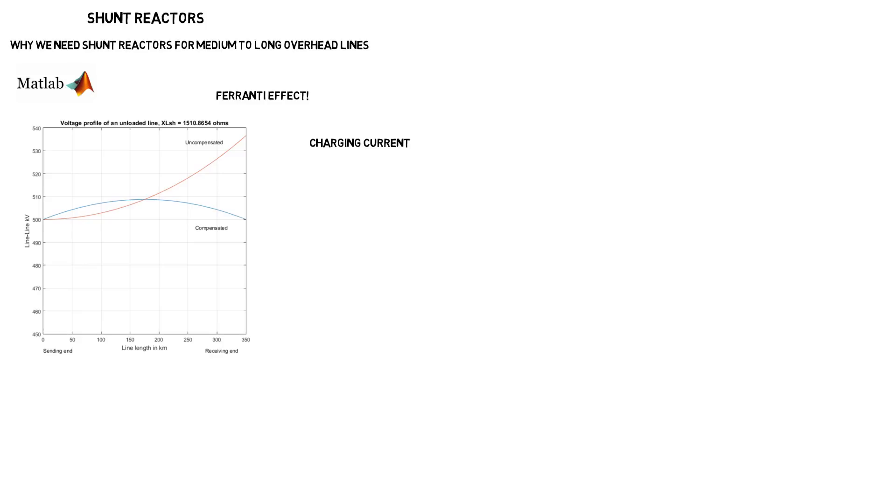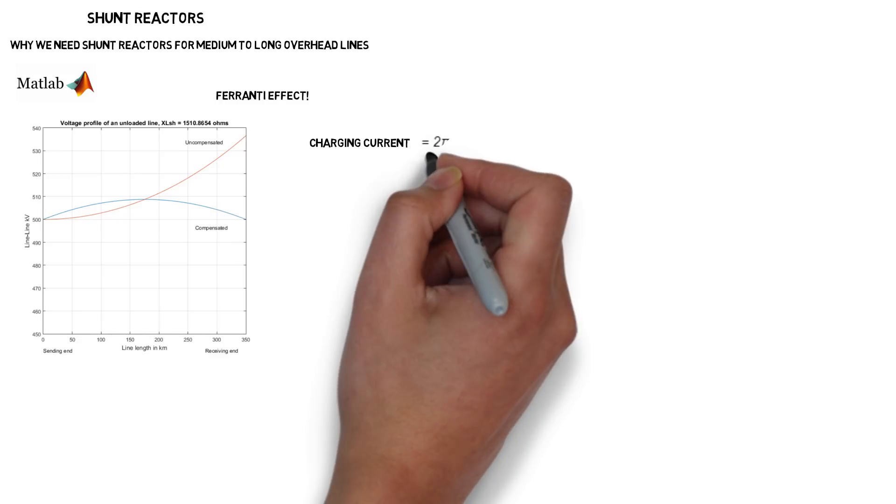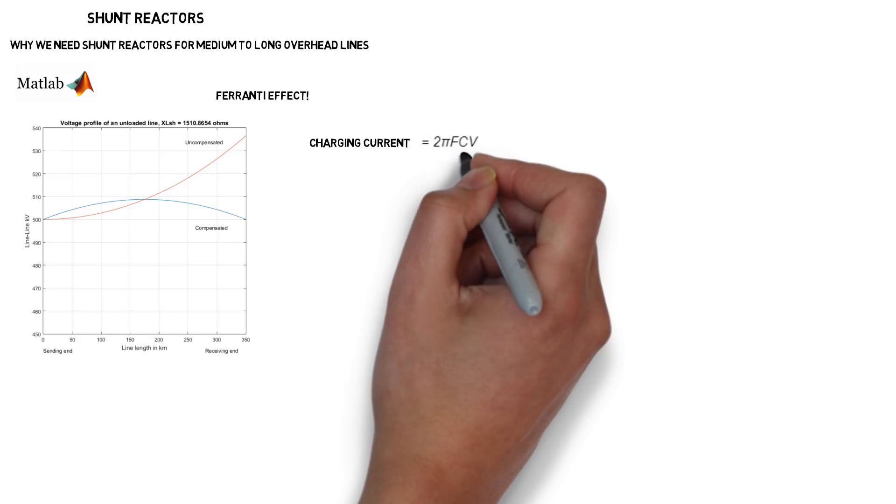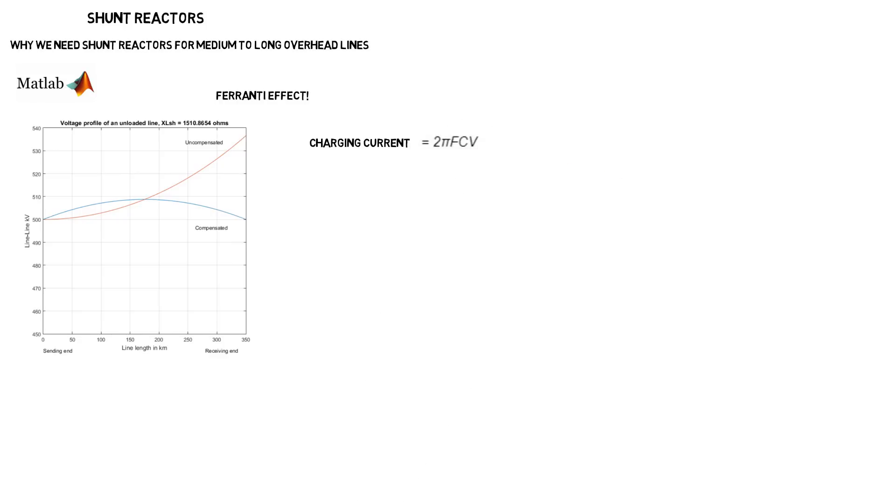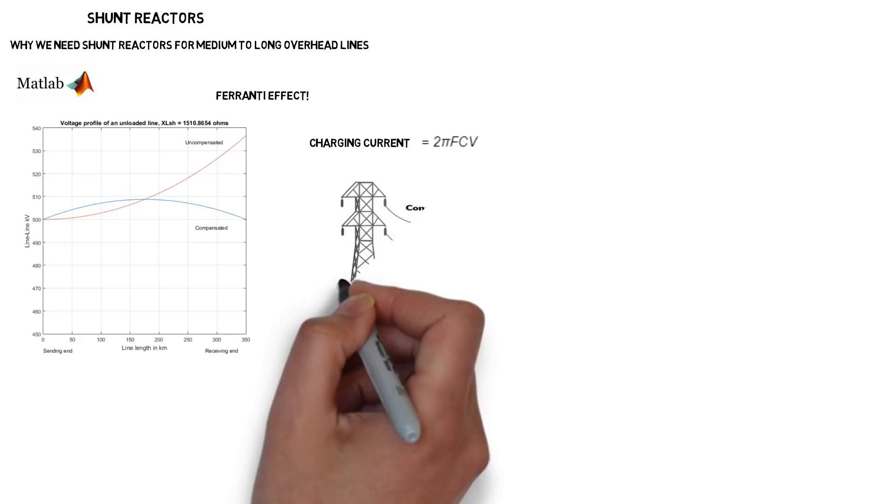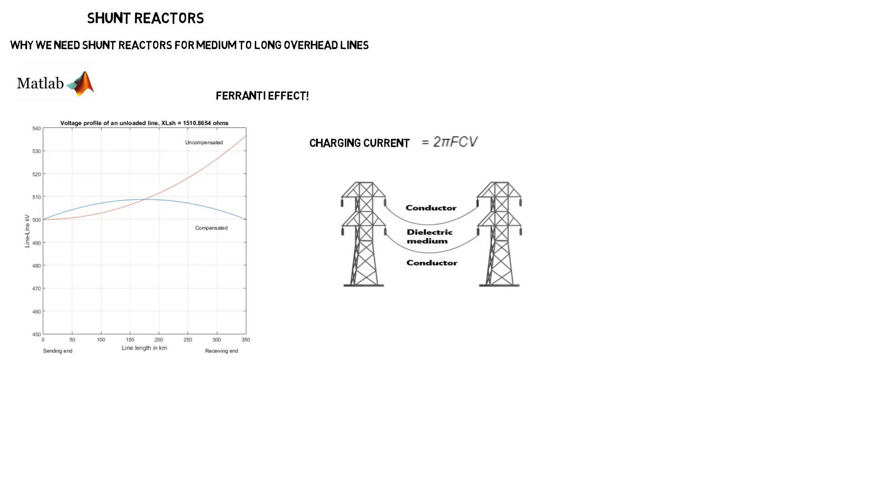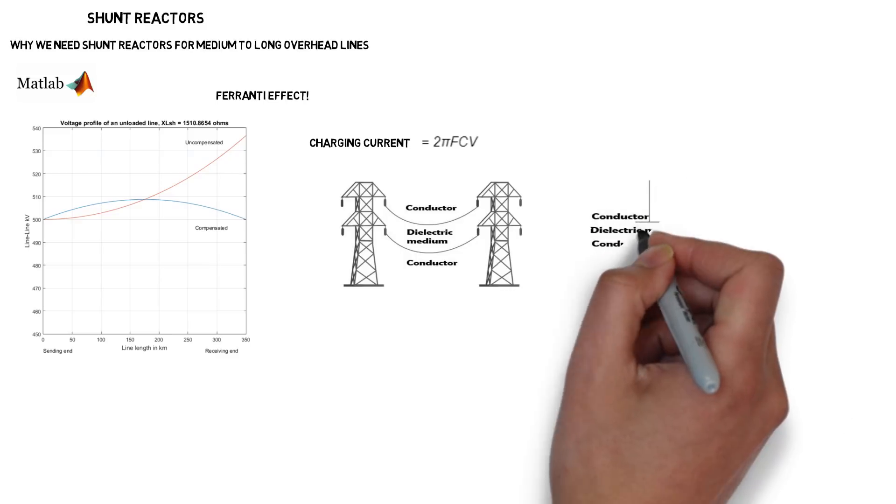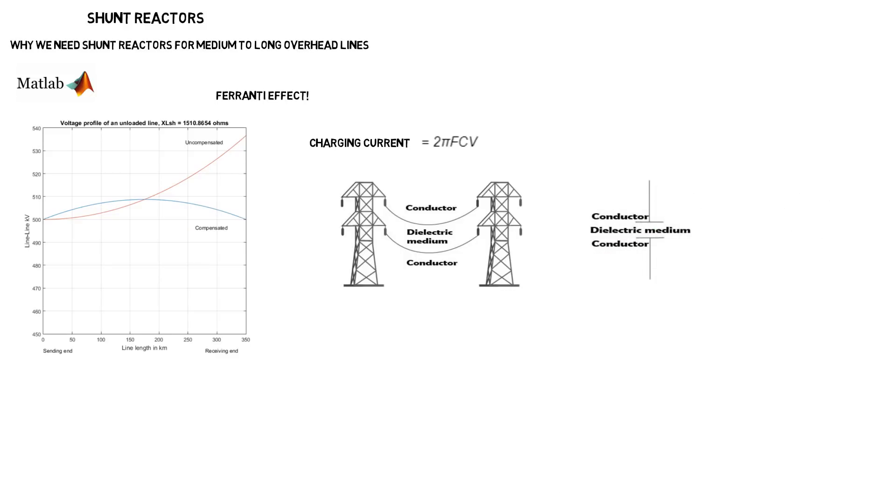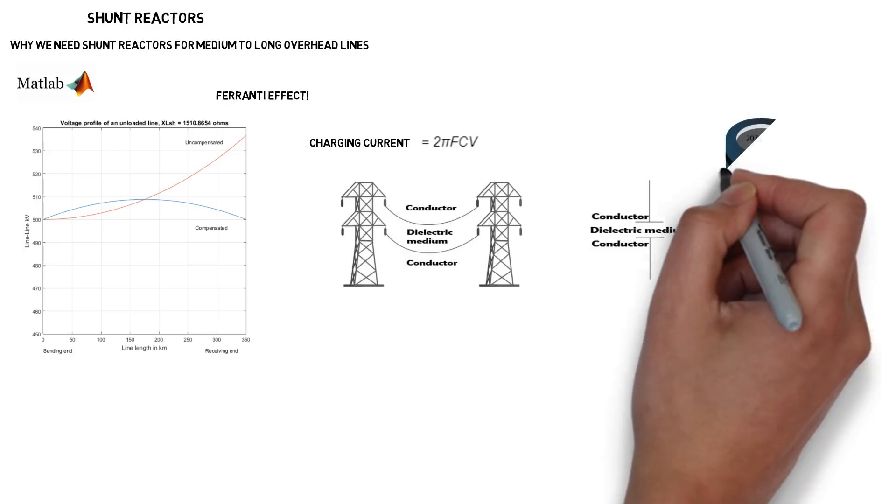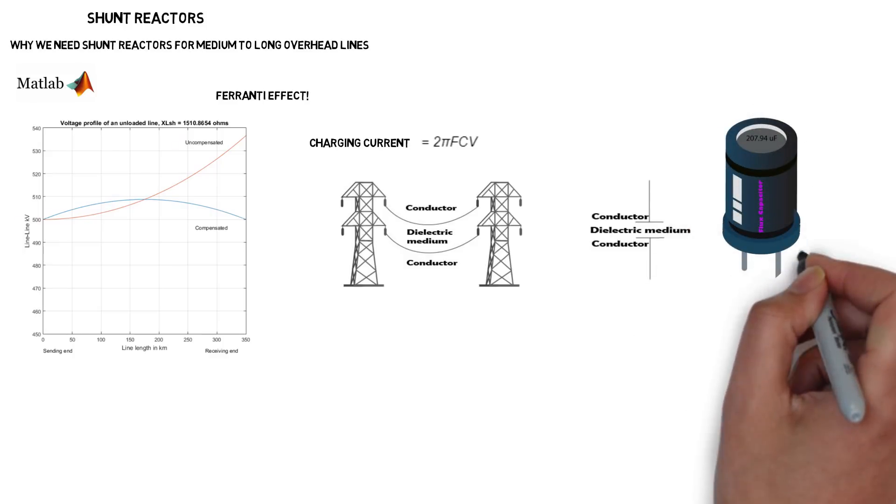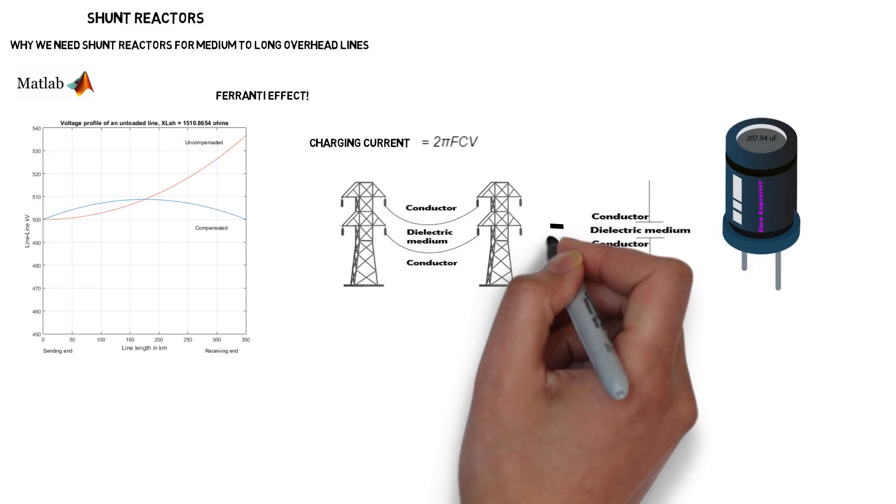The charging current is equal to 2πfCV, where f is the frequency, C is the capacitance and V is the voltage. Thus the Ferranti effect will be more onerous at higher voltages and frequencies. The capacitance of the line is due to its composition. We have conductors separated by a dielectric medium, another electrical component that has the same composition is a capacitor.